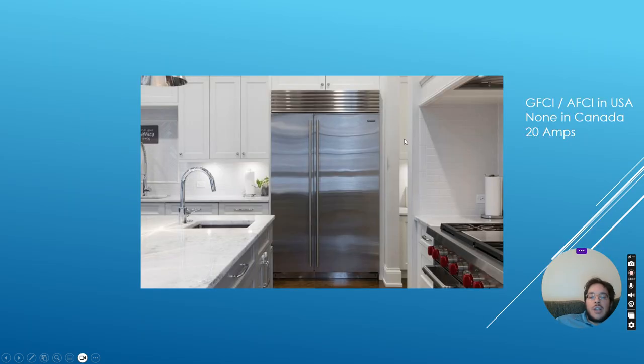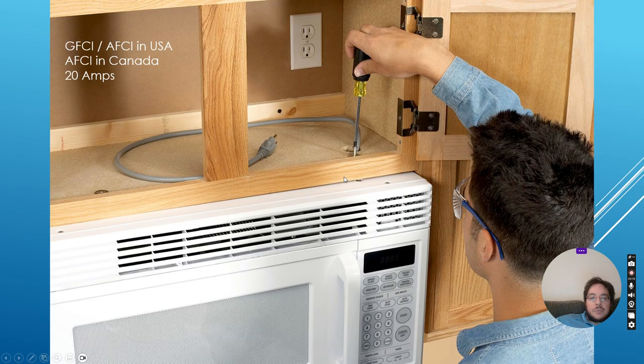And here's the deal. The fridge must have its own receptacle and its own circuit, and that goes behind the fridge. Now, in the United States, the receptacle must be GFCI, so ground fault, and also AFCI, arc fault protected. In Canada, it doesn't need any protection because they say, well, it's behind the fridge, so nobody's going to mess with it. It's not going to get wet or cause an arc fault. And it's got to be at least 20 amps. Well, 20 amps gives you plenty for the biggest fridge.